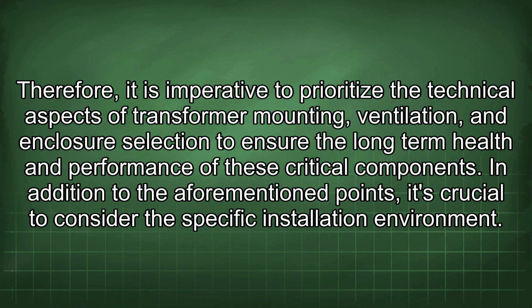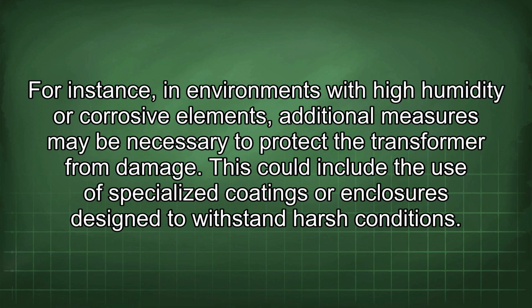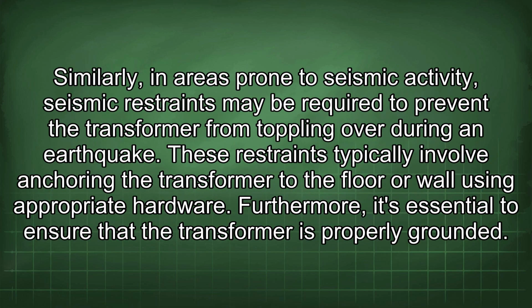In addition to the aforementioned points, it's crucial to consider the specific installation environment. For instance, in environments with high humidity or corrosive elements, additional measures may be necessary to protect the transformer from damage. This could include the use of specialized coatings or enclosures designed to withstand harsh conditions. Similarly, in areas prone to seismic activity, seismic restraints may be required to prevent the transformer from toppling over during an earthquake. These restraints typically involve anchoring the transformer to the floor or wall using appropriate hardware.